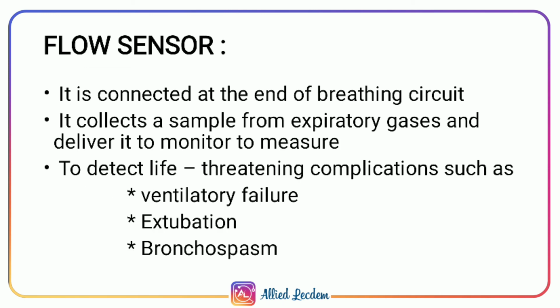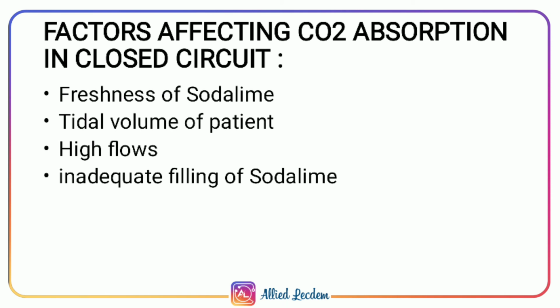Flow sensor. It measures the flow rate of liquid or gases delivered, and it is connected at the end of the breathing circuit. It collects a sample of expiratory gases and delivers it to the monitor to measure the flow rate. It is also useful in detecting some complications such as ventilatory failure, extubation, and bronchospasm. Factors affecting CO2 absorption in closed circuit: freshness of soda lime, tidal volume of the patient, high flows of gases, inadequate filling of soda lime.